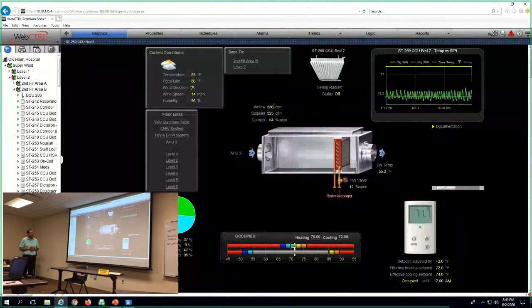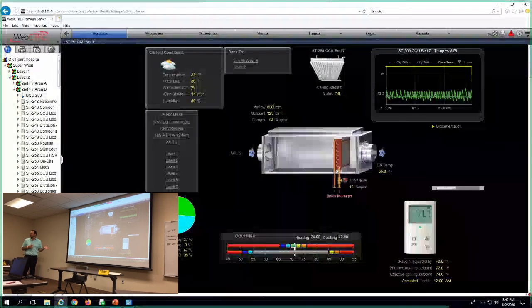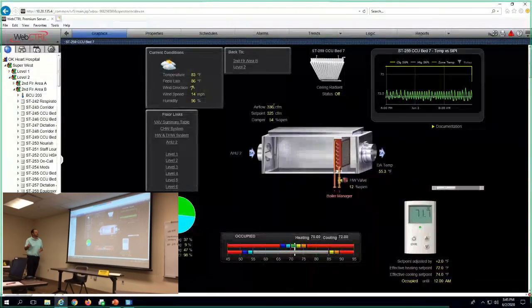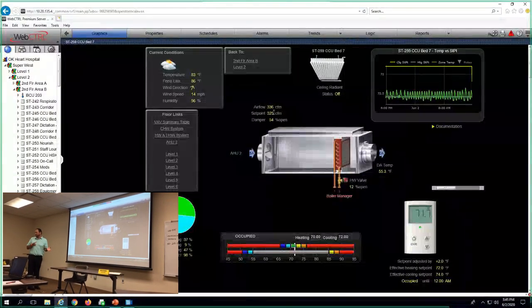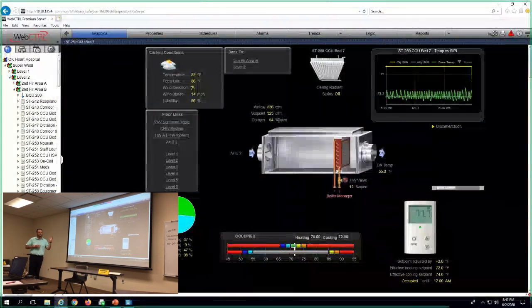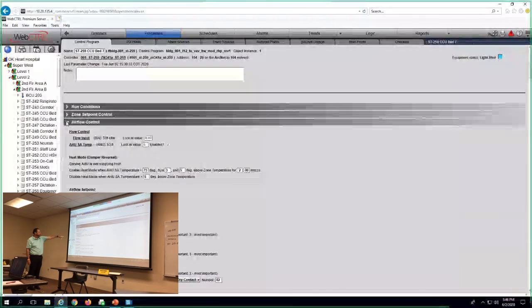Again, you can go and see what all those set points are if you want to drill down in the system. These numbers were provided by TME, and our test and balance team went out and calibrated every one of the VAV boxes and checked them, to make sure that when they say it's doing 325, it's doing plus or minus 10% of that. So we go up to the properties page. There's multiple ways to get to the airflow. You can go to the airflow control here, click on flow control.